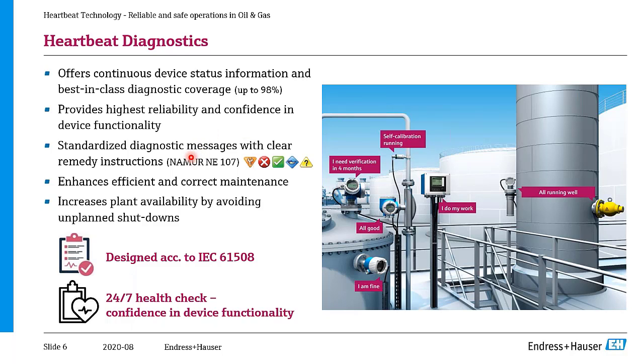It is not only that it's telling you that it has a problem, it is also that the messages you're getting are categorized according to the NAMUR recommendation number 107 with the status information and the categories connected to that. The purpose of this recommendation from the industry is that if something happens, you should know what happens and also what you should do when something happens. So no more error code 137 and you have to look for a manual. You get direct, clear text information: what happened and what should I do next.